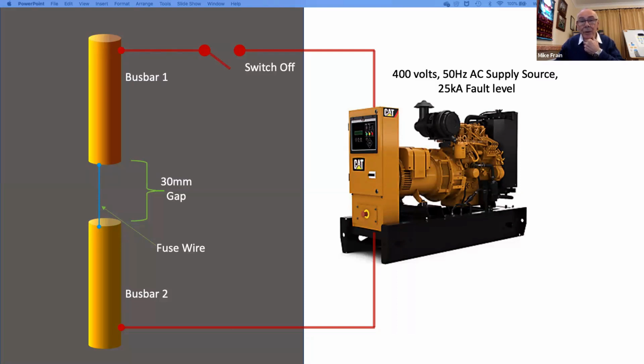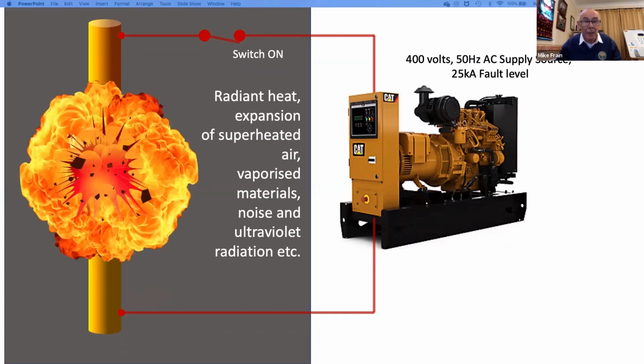It's the sort of output that you get from a 1000 kVA transformer, I suppose, in an industrial setting. As you can see, there's no protective device, just a switch, and connecting the two bus bars is a piece of heavy gauge fuse wire. When I ask electrical workers what will happen when I close the switch, they'll often say, well, a large amount of current will flow and the fuse wire will just simply rupture and rapidly disconnect the circuit. Well, actually, that's not what happens.